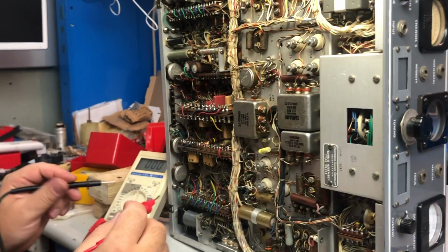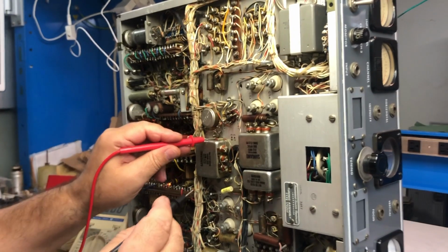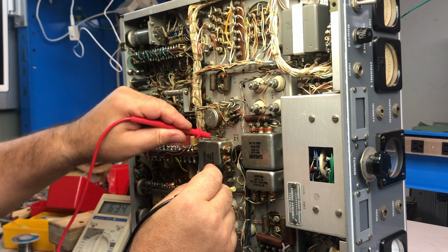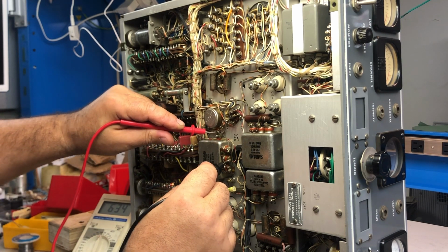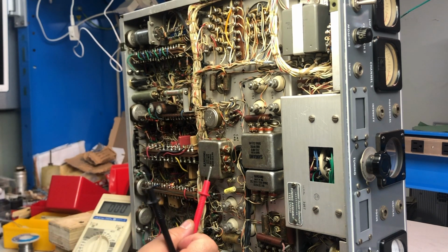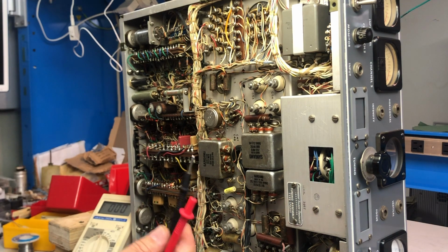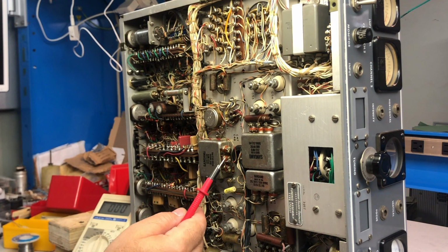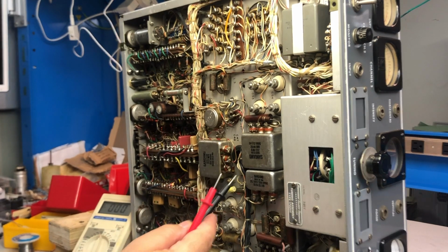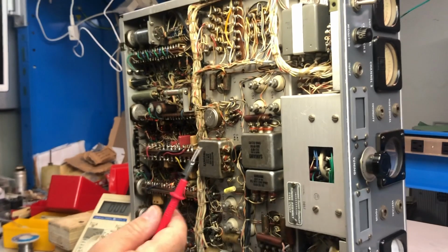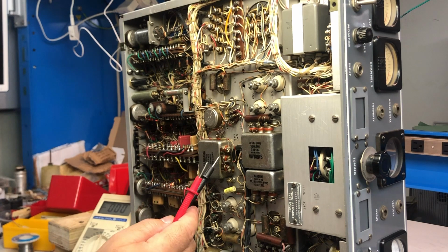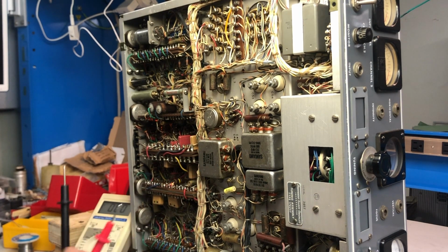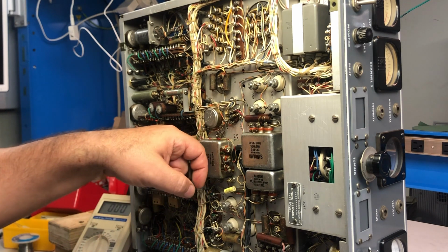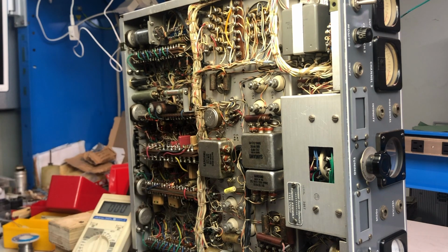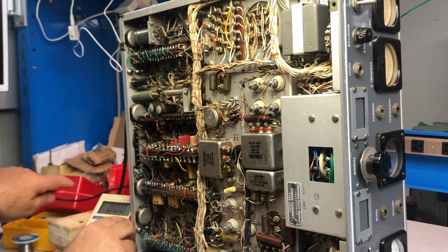However, if I go to measure the voltages, I'm measuring here at this capacitor 635 volts. This is rated at 600 volts. Seems that we might have a problem and this voltage is too high, and I have already removed this resistor in order to check, and it's perfect as well as this one. However, it might be that this is just underrated and becoming warm. So I think that the voltage is exceeding the rating and I need to replace it with something rated higher.